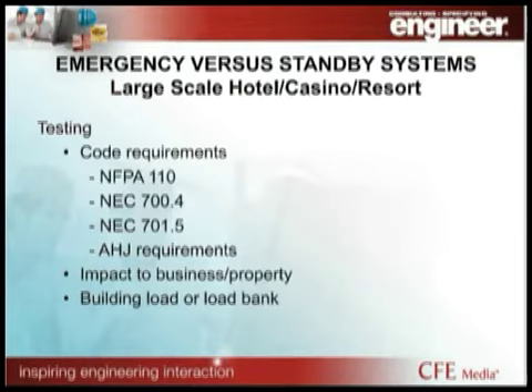really keeping a close eye on what happens with hospital generator testing. It's not really that way with your large-scale resort properties or other types of buildings. The local authority having jurisdiction is really probably your biggest driver on it. So setting a system up that can be tested with minimal impact to the business or the property is a huge benefit that I think you can incorporate much better with a large-scale aggregate paralleling system than you might be able to with a single transfer or multiple transfer switches, single generator, distributed versus aggregate.